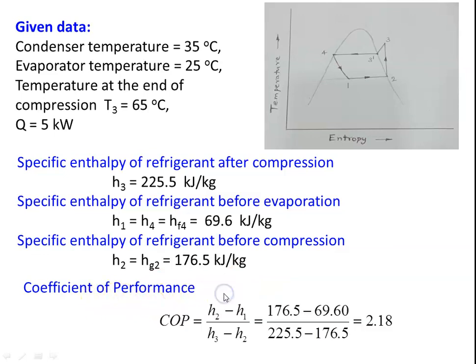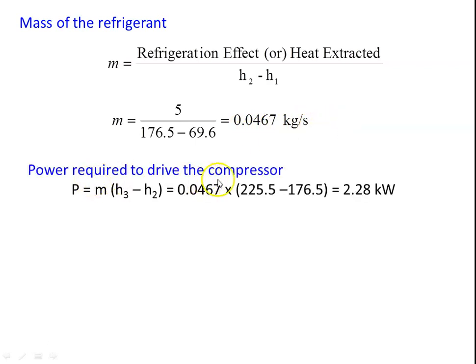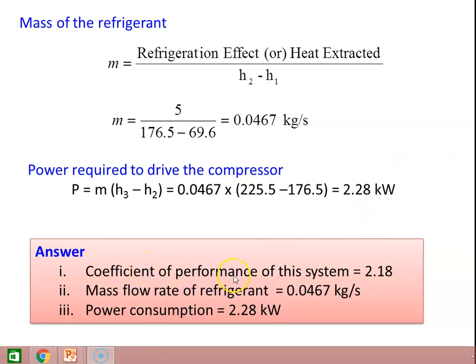The COP equation is H2 minus H1 divided by H3 minus H2. Substituting: 176.5 minus 69.6 divided by 225.5 minus 176.5, equal to 2.18. Mass of the refrigerant equals refrigeration effect divided by the enthalpy difference H2 minus H1 in the evaporator. The refrigeration effect is 5 kJ/s, so mass flow rate equals 0.0467 kg/s. Power required to drive the compressor P equals M into H3 minus H2, which is 0.0467 into 225.5 minus 176.5, equal to 2.28 kJ/s. Answers: COP is 2.18, mass flow rate is 0.0467 kg/s, and power consumption is 2.28 kilowatts.